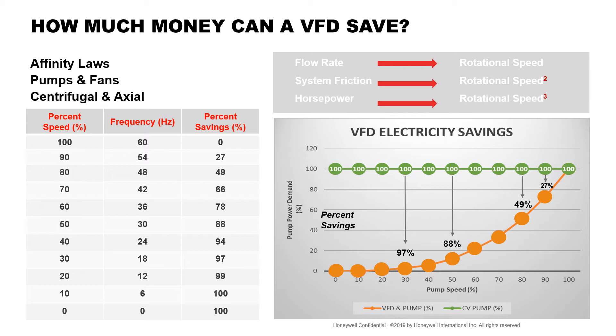Reducing the motor speed more and more will result in less significant energy savings as the curve begins to flatten out. We don't recommend running the motor at less than 30 Hz. At 30 Hz, there's an 88% energy savings, because the fan needs to run fast enough to cool itself.